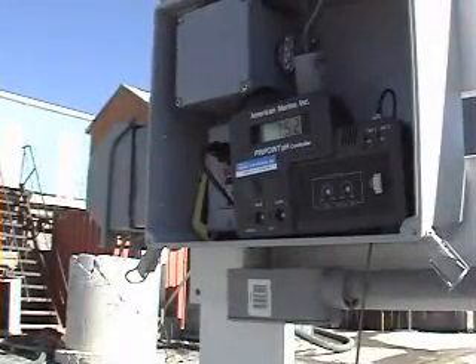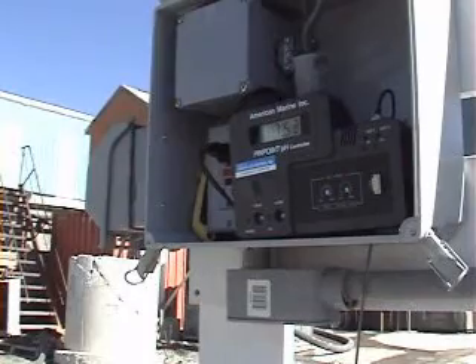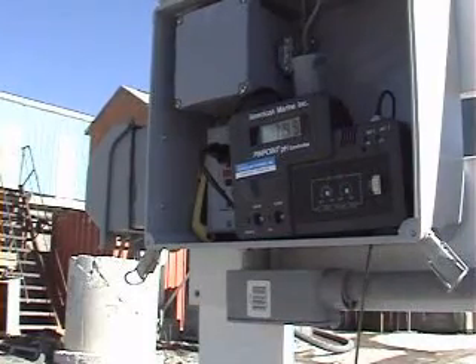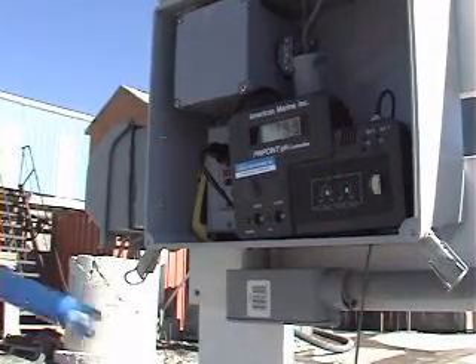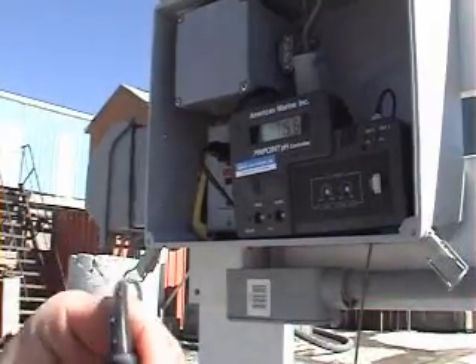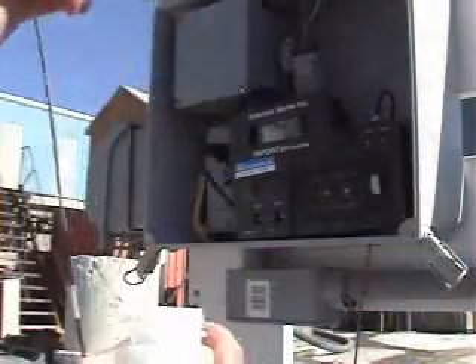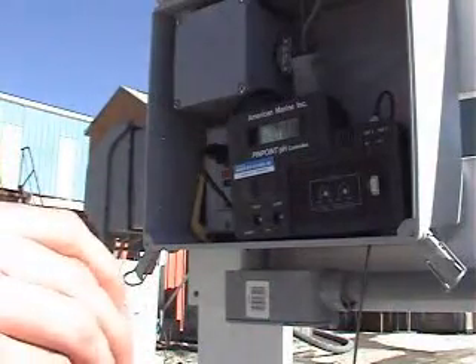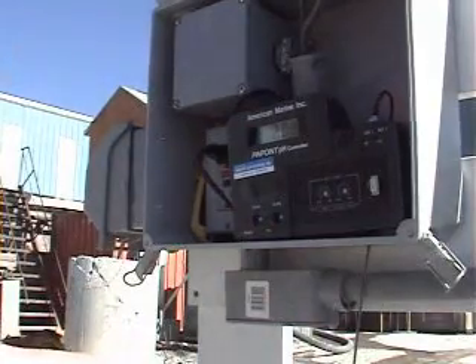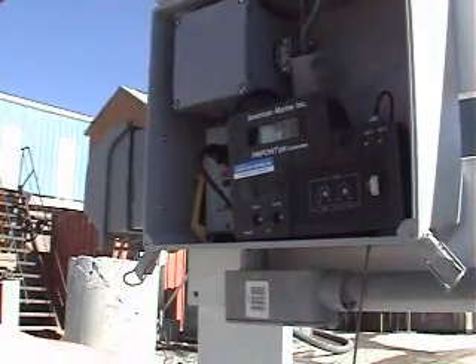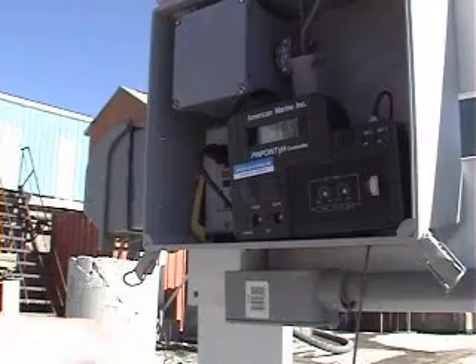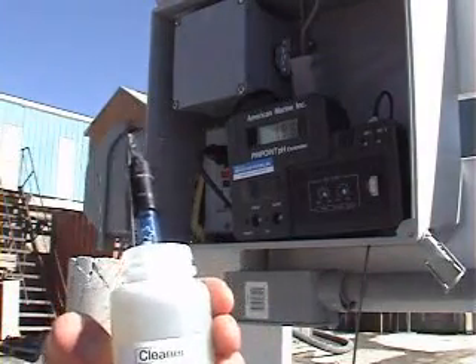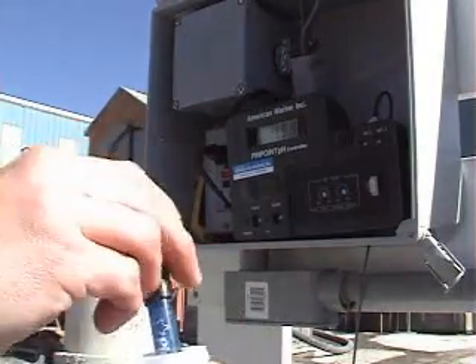Okay, now we're ready to go ahead and calibrate our pH WatchDog. I have the probe here. I'm going to start by actually dipping it in our cleaning solution. The cleaning solution will both remove any debris that we have on the probe and also any crystallization, any coating over the actual electrode ball. And normally you want to actually place the probe in the cleaner and let it sit for about a minute or two, but I've already done that, so I'm going to just give it a quick swirl around.